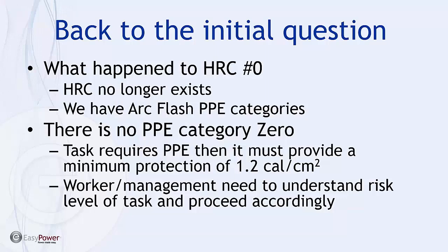So back to the initial question. What happened to HRC 0, Category 0? Well, first of all, HRC as a reference or as a table or even as a list of categories no longer exists. You'll see in all the table labels and all the instruction that they refer to these as arc flash PPE categories. So it's not so much that it's a trick question. HRC as a categories table no longer exists. There is no PPE Category 0, and I think that's evident of the fact that if it's less than 1.2 calories per square centimeter, that doesn't mean there's no arc flash danger there.